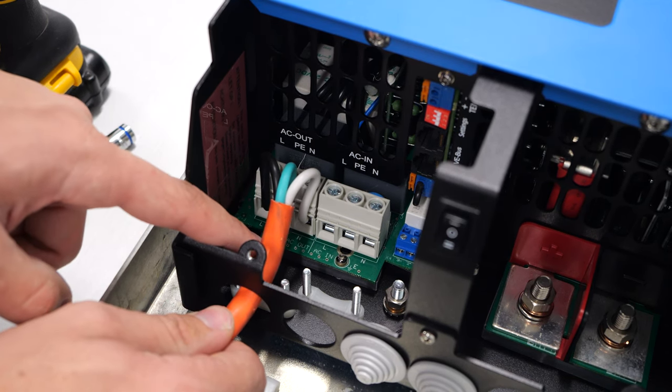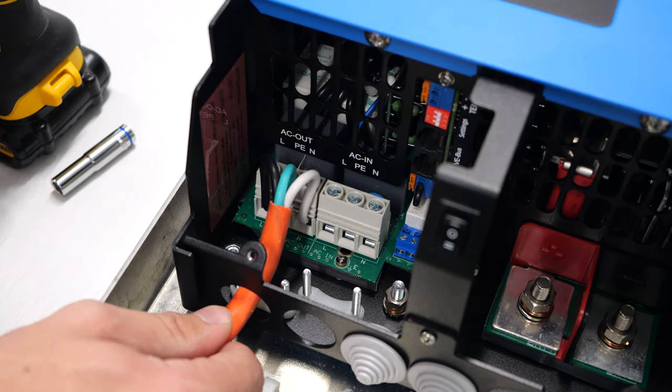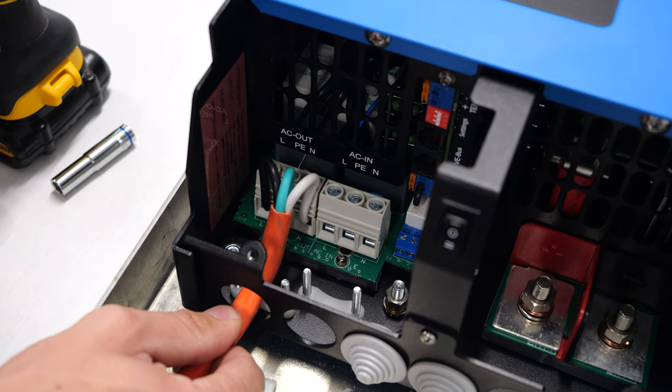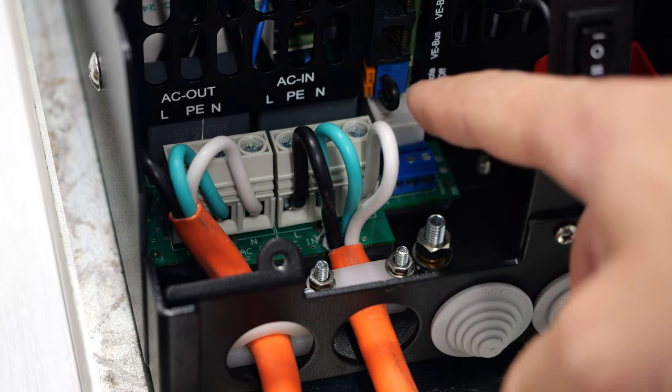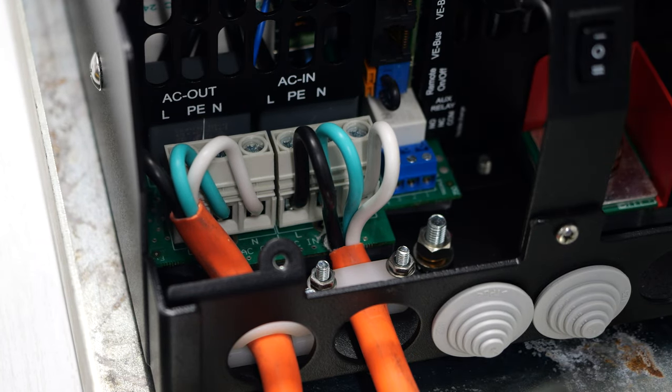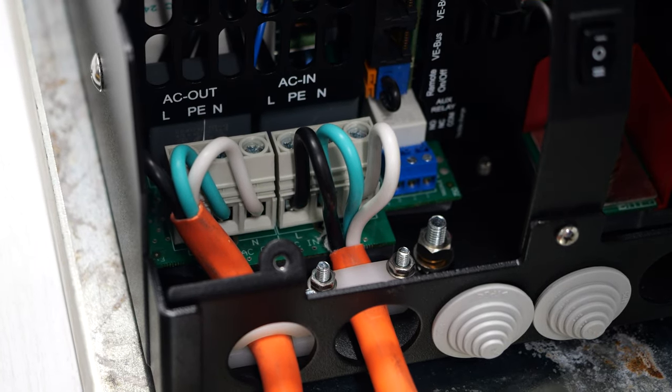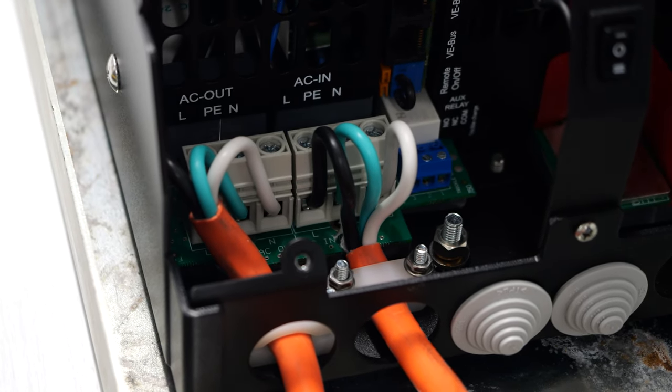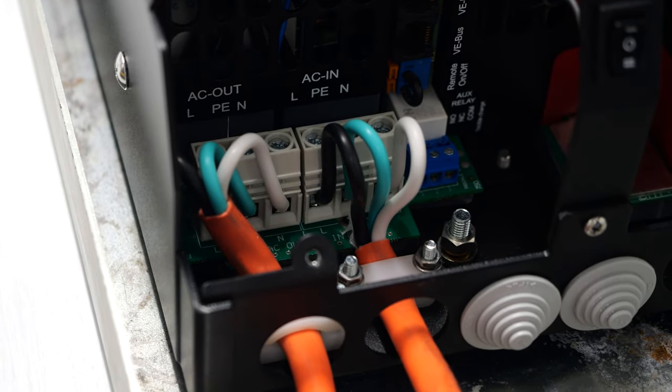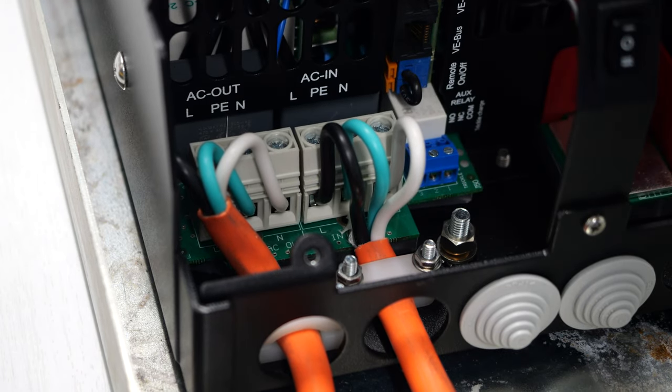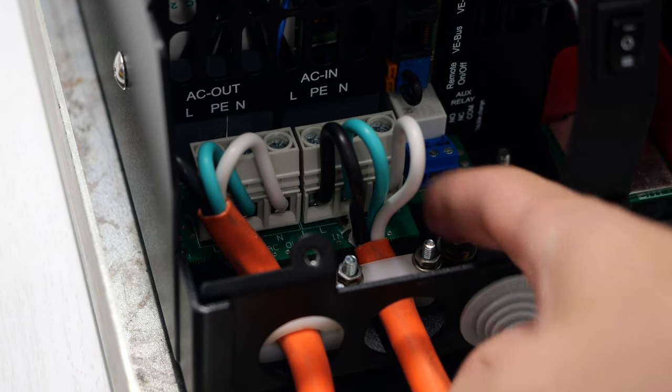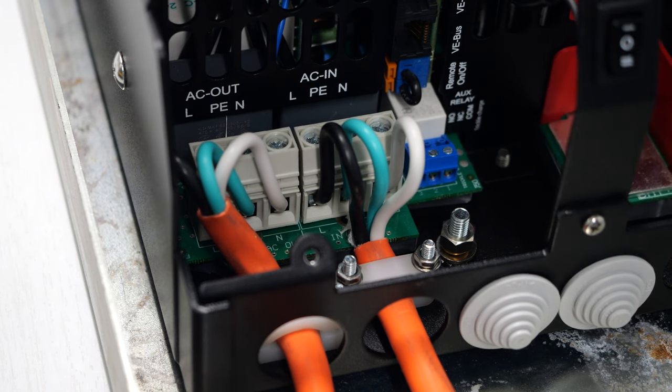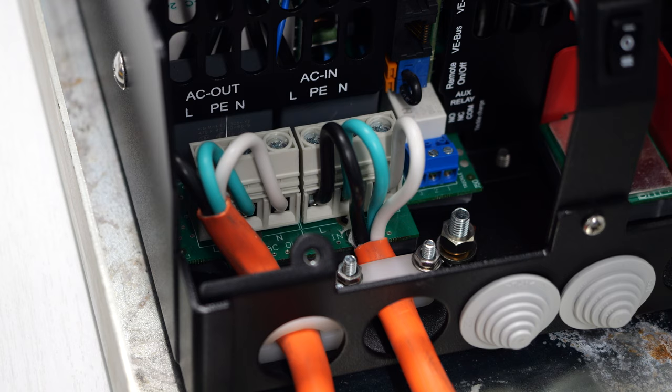Once those screws are in, I'm actually going to shove some more cable in here so that I could bite down on the insulation of my cord with that clamp. I have a little bit of extra in here so it's not just cut at the absolute shortest length possible. Now I got those connections in. That's really nice because if these cords ever get pulled, there's no extra stress on the terminals. Some guys make these as short as possible, and I don't like that because if the cord gets yanked, it's immediately putting the stress right on the connection point.